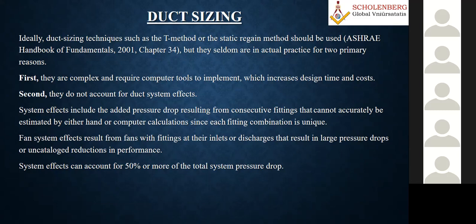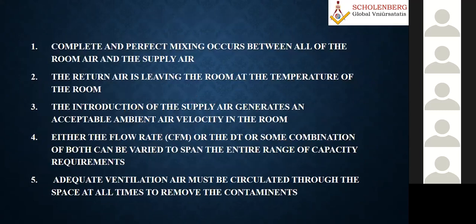But every method has its own advantages and disadvantages. Particularly the static regain method has its own pros as well as cons. This I have just given; you know all the things in that. But all the things we are doing with certain assumptions, because complete and perfect mixing occurs between all of the room air and the supply air, and the return air is leaving the room at the temperature of the room. It may not be true.